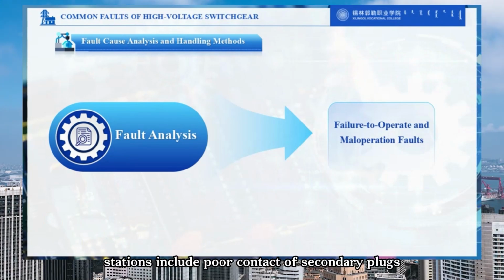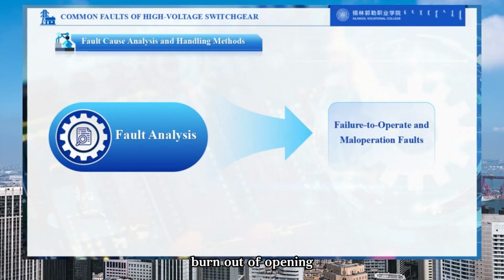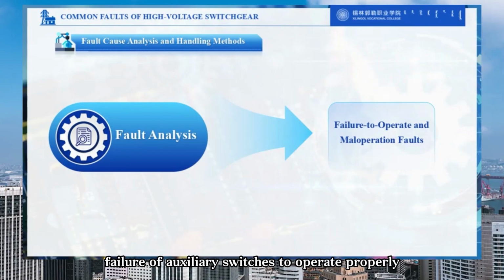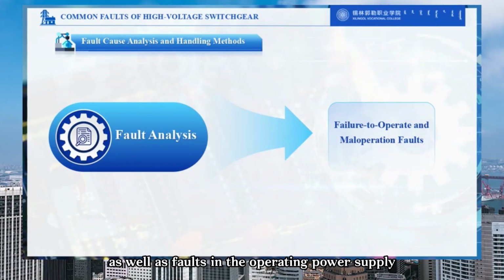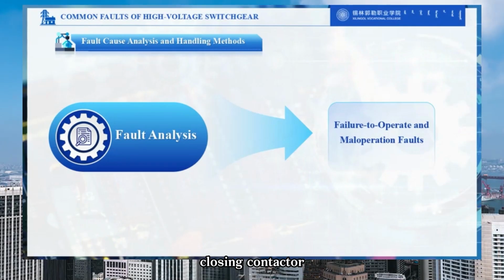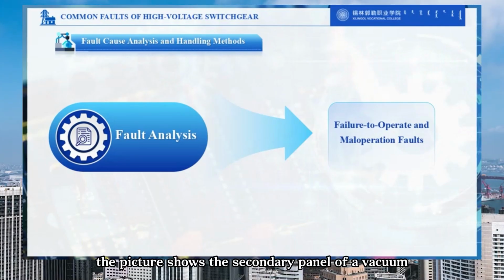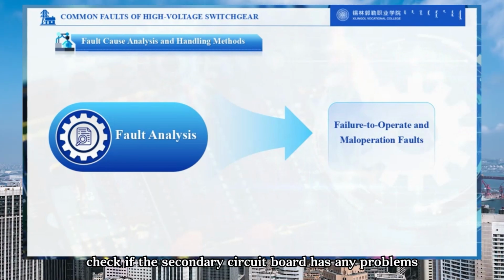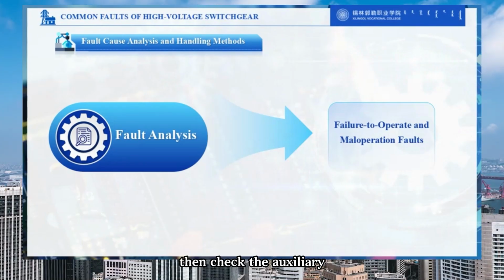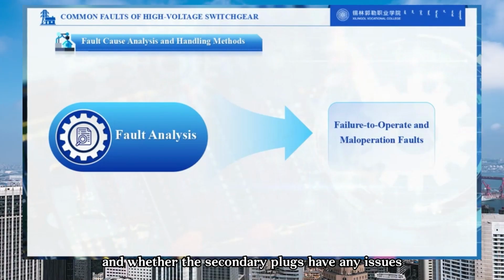Manifestations include poor contact of secondary plugs, loose terminals, wiring errors, burnout of opening and closing coils due to mechanism jamming or faulty transfer switches, failure of auxiliary switches to operate properly, as well as faults in the operating power supply, closing contactor, micro switches, etc. The picture shows the secondary panel of a vacuum circuit breaker. First, check if the secondary circuit board has any problems. Then check the auxiliary contacts and energy storage contacts and whether the secondary plugs have any issues.